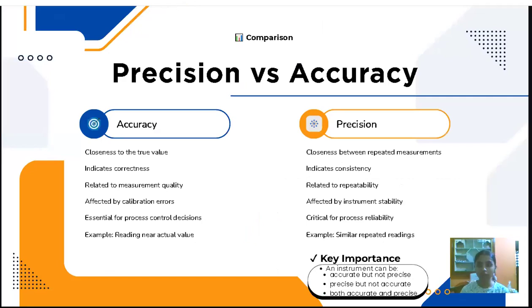Now, precision versus accuracy. Precision and accuracy are related, but they are different concepts in measurement. Accuracy shows how close the measurement is to the true value, while precision shows how close repeated measurements are to each other. So, accuracy indicates correctness, precision indicates consistency. Accuracy is related to measurement quality, precision is related to repeatability. Accuracy is affected by calibration errors, precision is affected by instrument stability. Accuracy is essential for process control decisions, whereas precision is critical for process reliability.